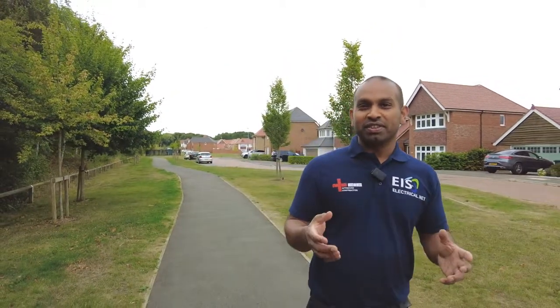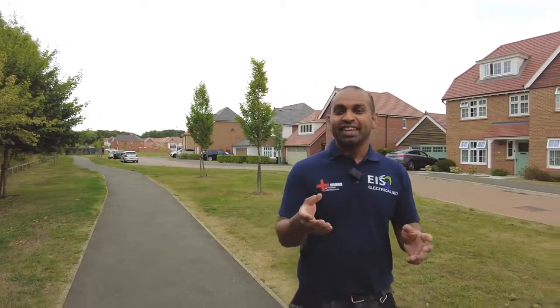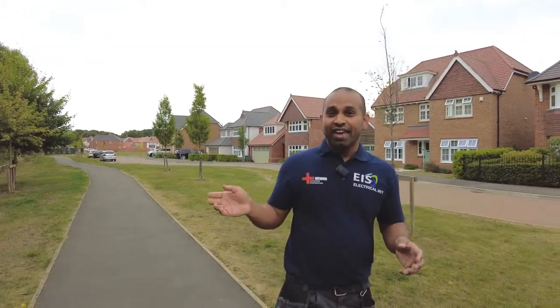A couple of weeks back I had a call from one of the customers who live just down the road — they were having a Pod Point EV car charger installed and they wanted the RCD device in the fuse box changed to a type A RCD. Pod Point is a nationwide EV charging company; they don't really do changes to fuse boxes. So I went in and helped that customer get the RCD replaced, and at the same time they had a problem with their house alarm, which I sorted out as well.